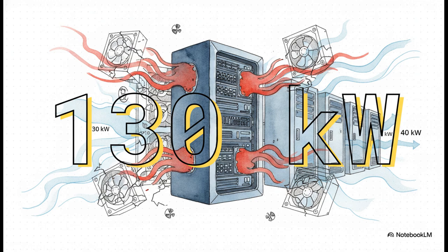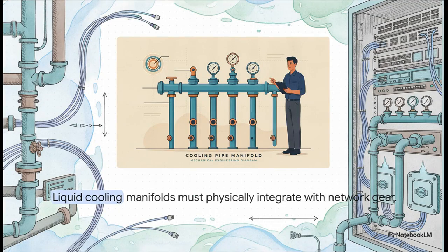A single state-of-the-art AI rack, like the NVIDIA GB200, draws over 130 kilowatts. To put that in perspective, that is more than 3 times the maximum limit that traditional air cooling can even handle. Standard data center air conditioning ceilings out at roughly 30 to 40 kilowatts per rack, we have blown completely past that limit. And this intense physical reality forces us right into direct liquid cooling.